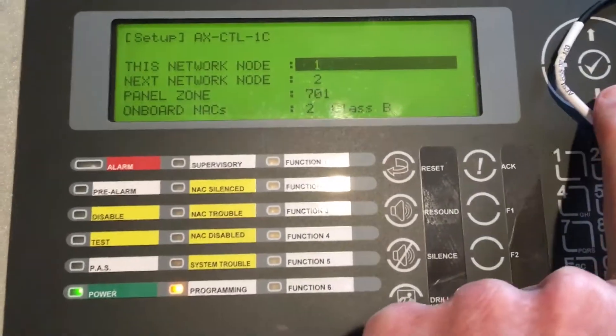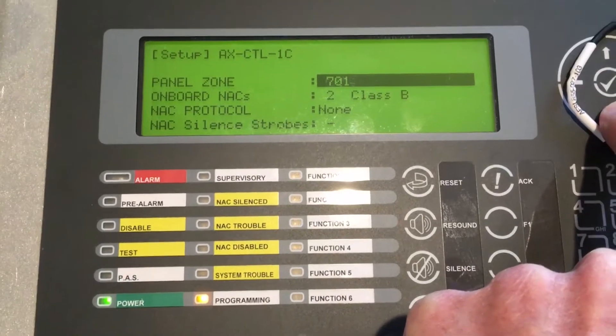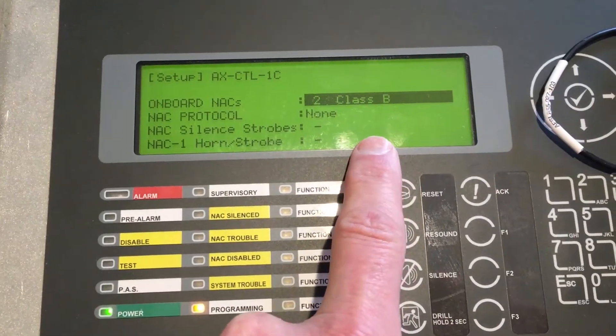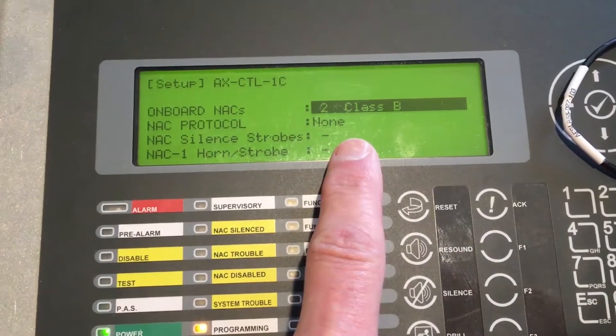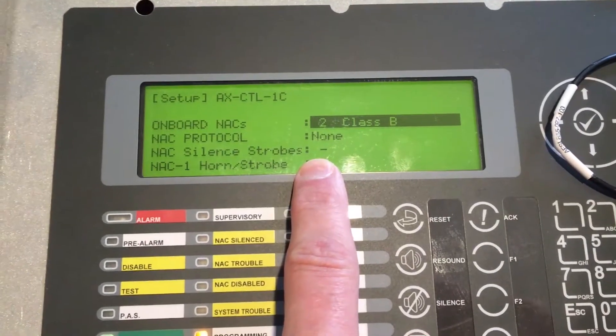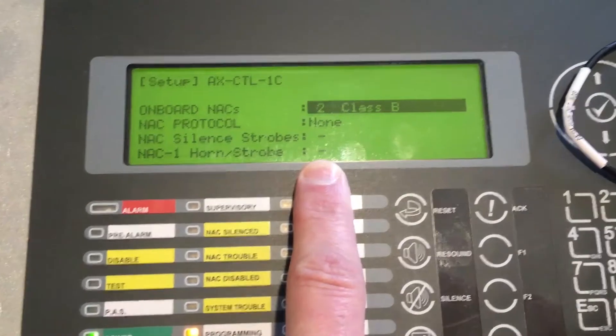On the setup screen we're going to scroll down a number of times until we see onboard NACs. Onboard NACs are currently set for two Class B circuits. This is a one-loop fire panel and it does only have two NAC circuits, but currently there's no protocol — we're not going to be turning our horns and strobes off on silence. There are no check marks or any modifications to any of those items.